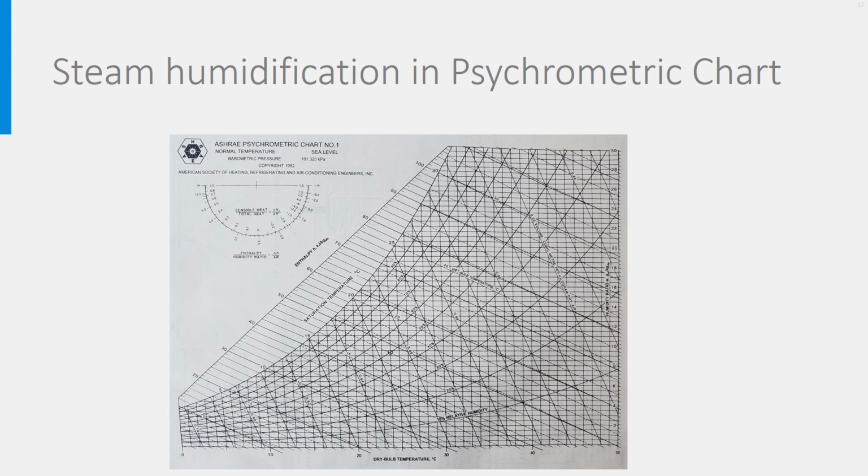If we look at the process in the psychrometric chart, we plot here again point 1 and then the line of constant absolute humidity of 6.8 gram. Then we need to go first to the protractor above and draw here from the point in the middle the line of dH over dx is 2675, expressed in the protractor as 2.7, so divided by 1000. We draw then a line parallel to this one, but starting from point 1. At the intersection, we'll find the final point 2.